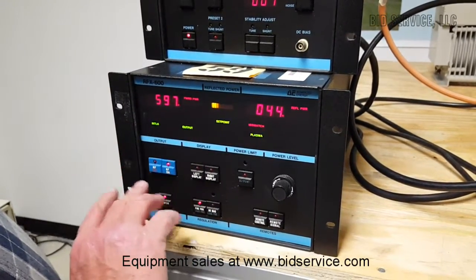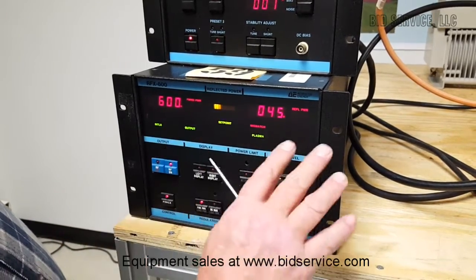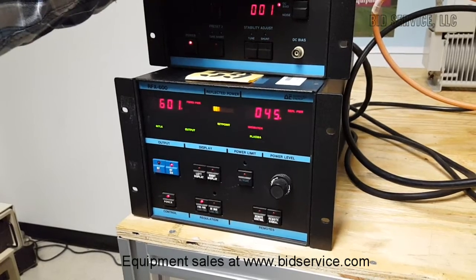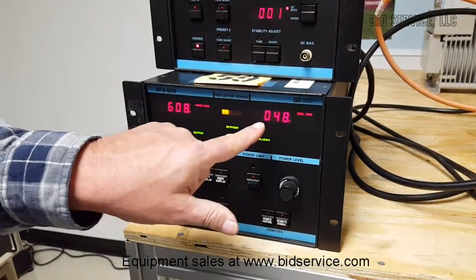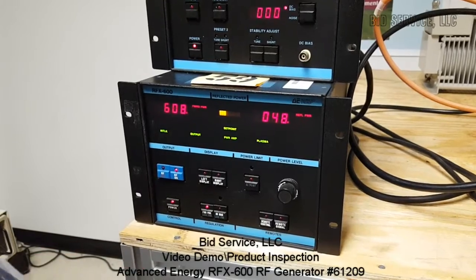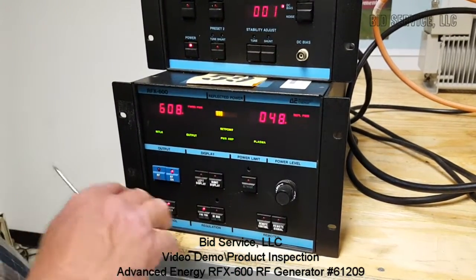I wanted to point out that I can put this at max power — you can see we're at 600 watts and we've got a reflected power of 45 watts. I have a little mismatch there; I should be able to clear that up. So we have a reflected power of 48 watts, which is less than 10%, so that is acceptable for this tuner.